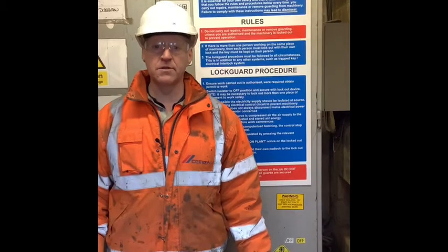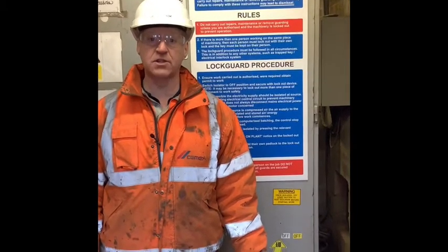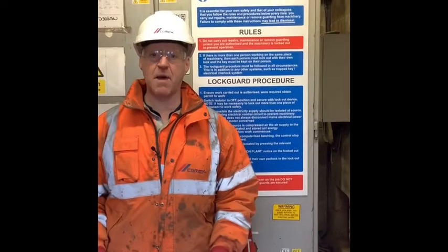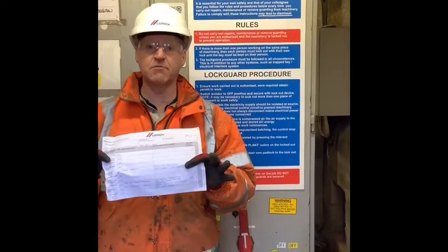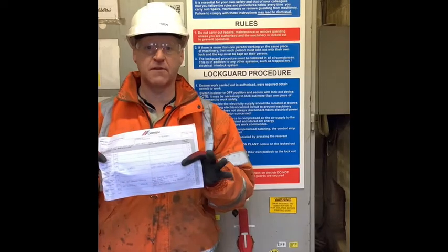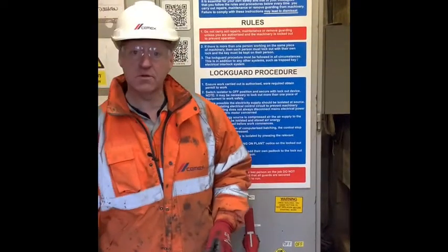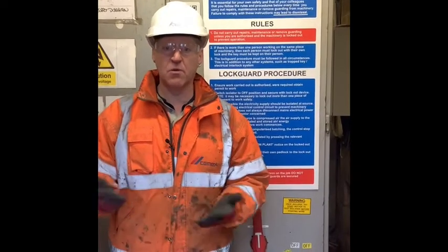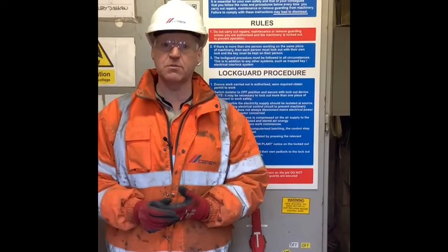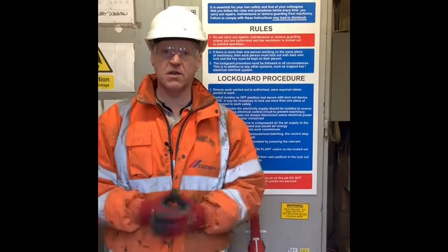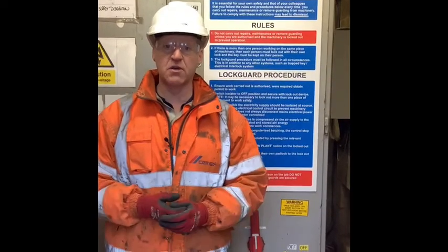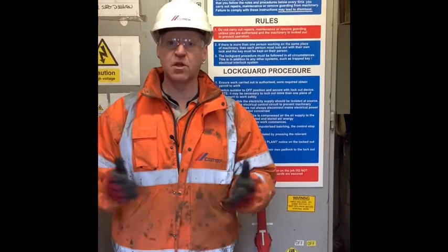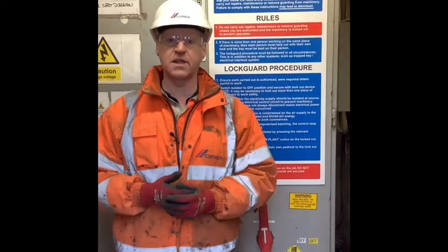We're now going to move on to practically checking the bag filtration system. So an hour ago, Cheddars and myself went up to the baghouse and we did a dynamic risk assessment. We completed our work safe. Out of those items, we've identified we could come into contact with moving material or moving machinery. There are slips, trips and falls, access and egress to the bag filtration unit, and also adverse weather. We don't want to be going up there when it's windy. So the first thing we need to do is fully isolate the plant.